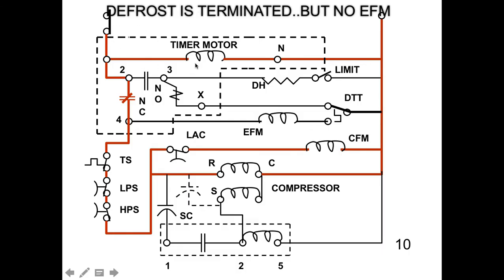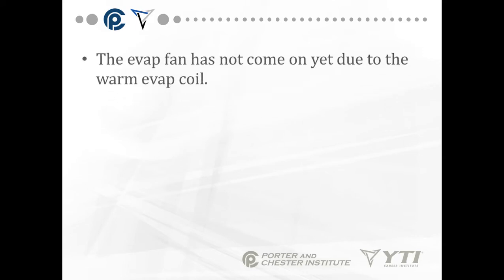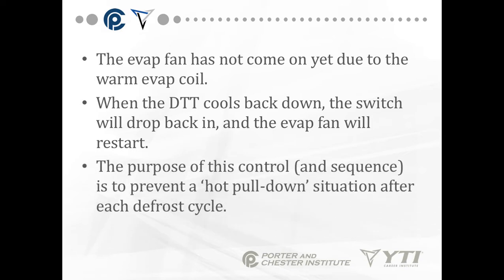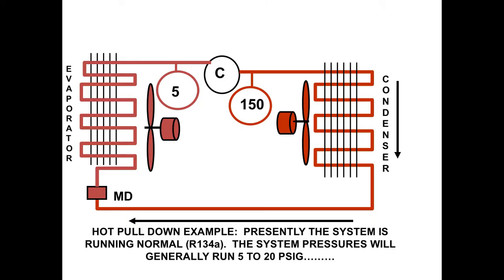When the single pole double throw DTT senses the evaporator coil is warm enough, it will switch up to the top circuit, completing the path to the clutch or termination solenoid on the defrost time clock. The solenoid will swap the contacts back into refrigeration mode. In other words, there's no waiting for the time delay. We actually force the system back into cooling mode. Now the defrost is terminated, so we're back in cooling mode. 2 to 4 is closed. 2 to 3 is open. My compressor is now running. But notice my EFM has not started to run yet. That's because the DTT senses the coil is still warm.